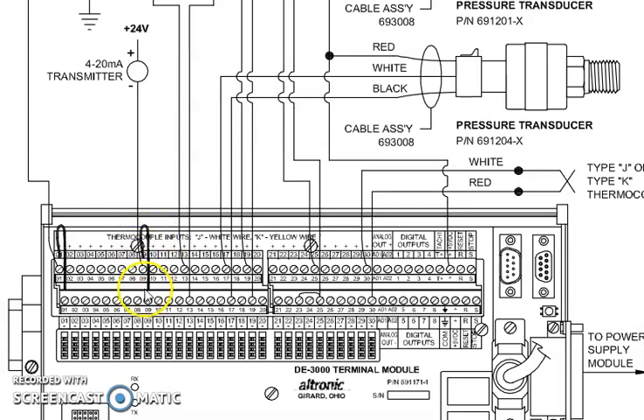So that's what this jumper wire is doing. We're taking the signal in 4 to 20 milliamps and landing it at terminal, in this drawing 9, and then we're jumping the two terminals together with a jumper wire, and then internally this terminal is connected to ground with a 200 ohm resistor. So we're converting the signal from 4 to 20 milliamps to a 0.8 to 4 volt range. And that's really neat to know when you're doing some testing out on site, so you don't have to break your wire and actually measure the amperage. You can simply do a voltage test.